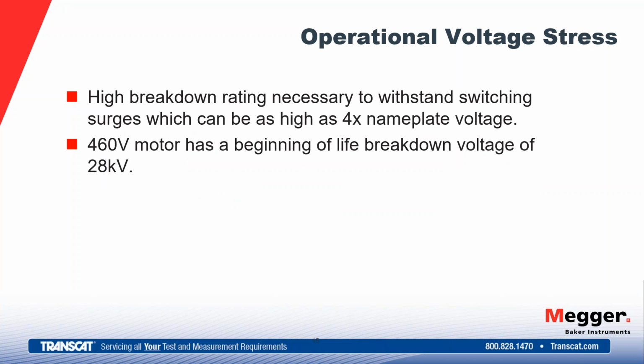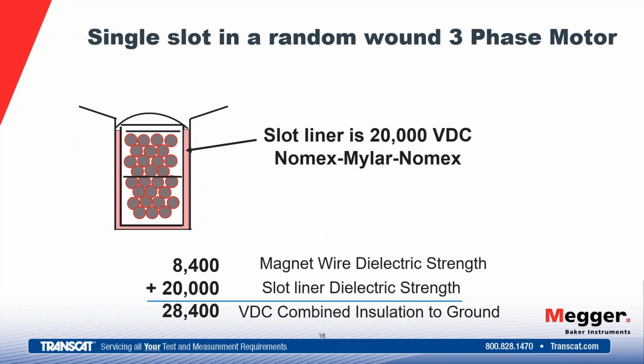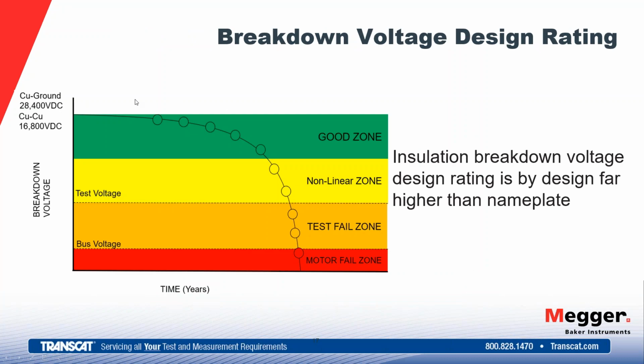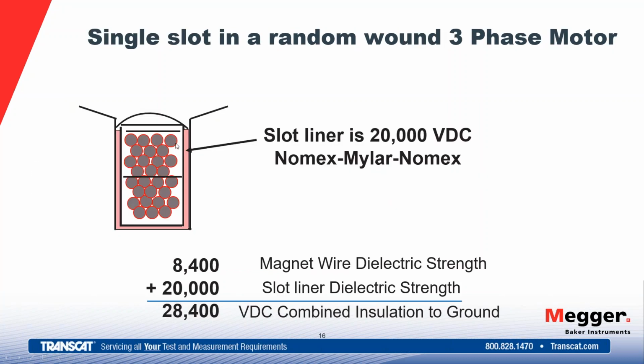So operational voltage, again, requires a high breakdown rating necessary to withstand the switching surges, which can be as high as 4 times nameplate. For instance, for a 460 volt motor, at the beginning of life, its breakdown voltage is 28 kV. So here's where we come from with those numbers. Here we see basically one slot of a stator with wire in it. The red part here is the insulation around the wire. This pink part here would be our ground wall insulation in the slot. So here's basically a cross-cut view of a slot of a motor.